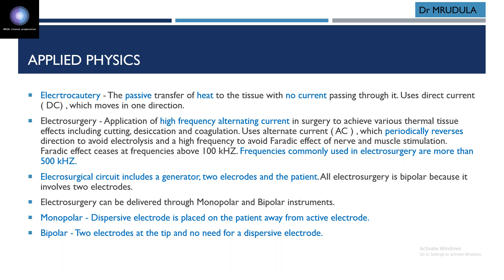Now, the generator of the electrosurgical unit functions as a conversion of low electrical frequency of mains to high frequencies, because as I told you, frequencies involved in electrosurgery are more than 500 kilohertz and up to 3 million hertz. So the generator mainly acts as a converter that converts low frequency currents to high frequency currents. It adjusts the wattage and indirectly the voltage, and also controls the duty cycle.